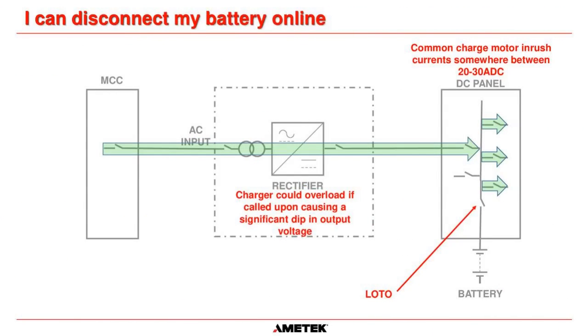So in that system, if you remove the battery by locking out this breaker here, yes, in normal operation, your load circuits are going to remain powered and you're not going to have a plant outage situation. But if you then have a fault on one of these branch circuits and the tripping and closing coil springs are called into action, the common charge motor inrush can be somewhere between 20 to 30 amps DC. Okay, so that sudden inrush, and it actually can be more, may cause an overload on the output of this charger. And the only way a charger can prevent an overload is by reducing its output voltage. So if one or more tripping and closing coil springs come on at one time, that is going to severely overload the charger. It's going to cause this voltage bus to drop, and it may cause the other load circuits connected at the DC panel to drop out as well.